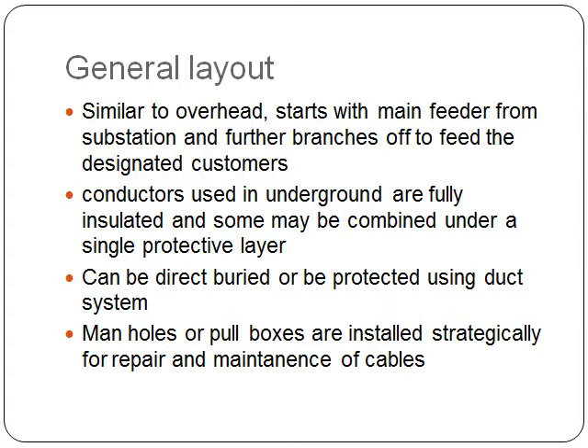The general layout, similar to overhead, starts with a main feeder from the substation and further branches off to feed the designated customers. The conductors used underground are fully insulated and some may be combined under a single protective layer. It can be directly buried or protected using a duct system. Manholes or pull boxes are installed strategically for the purpose of repair and maintenance of cables.